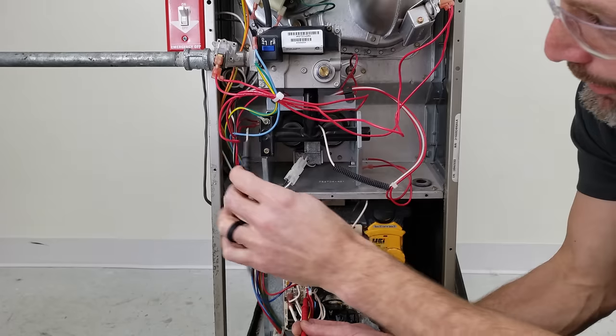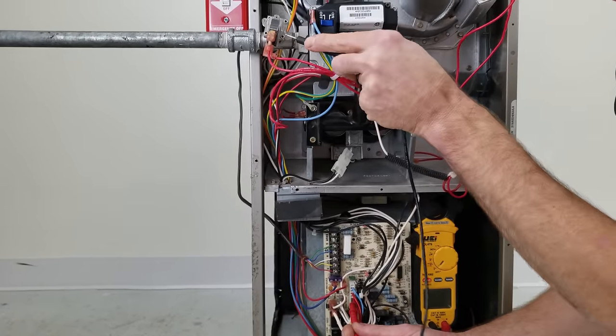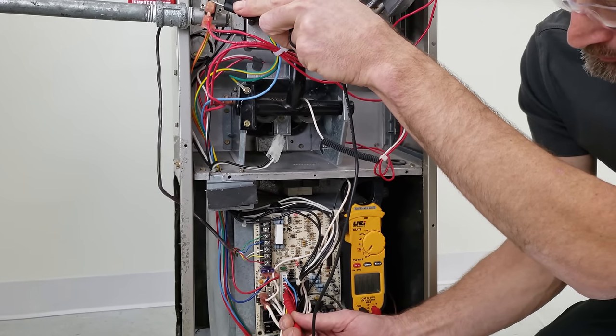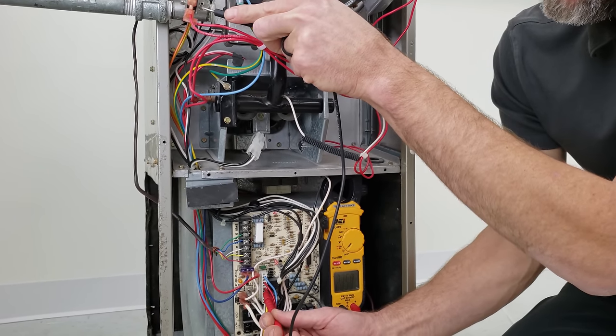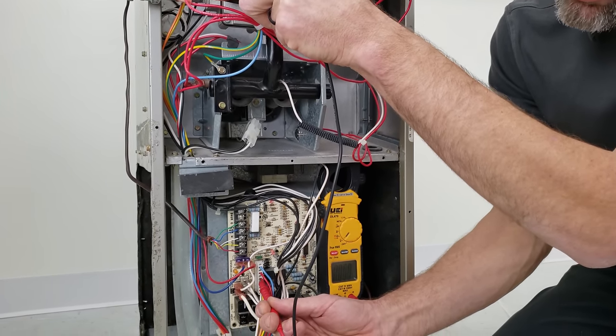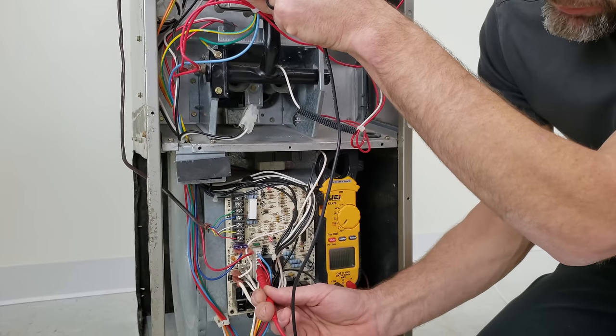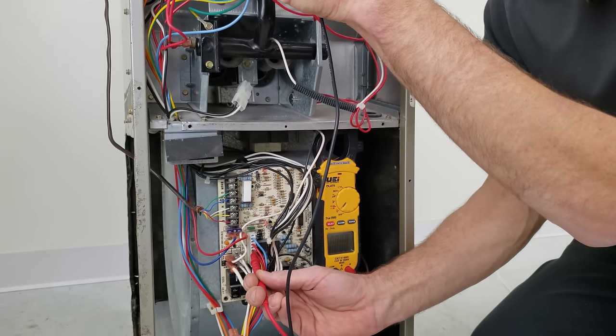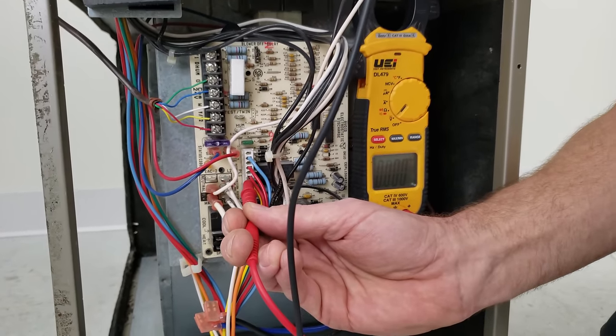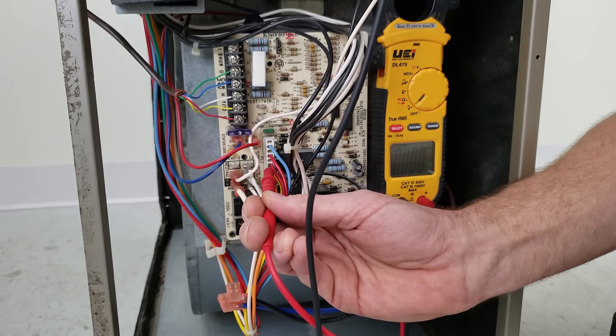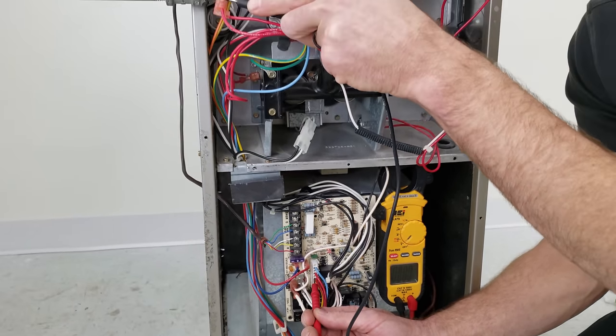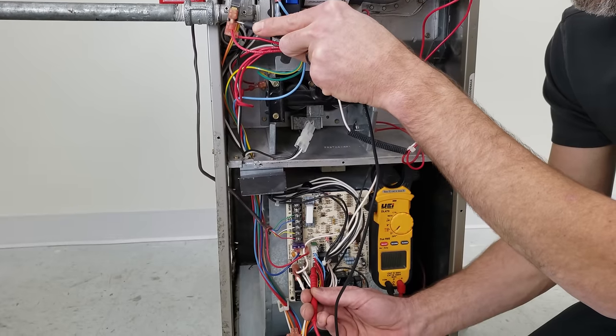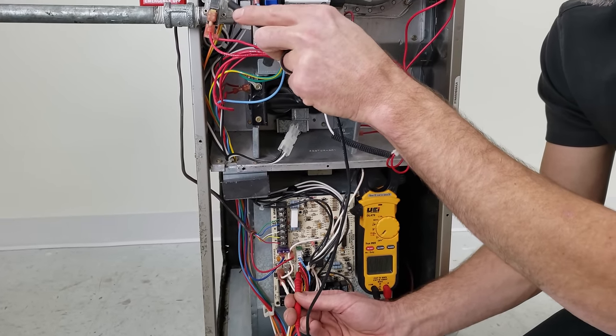Now we're gonna take our measurement point from over here on the low pressure switch. And you see we're measuring 26 volts at the input. And on the other side of the switch, you see we're measuring 0 volts. So right now, our low pressure switch is the one that's at fault, or we have no propane in the tank, which has caused this low pressure switch to open up.